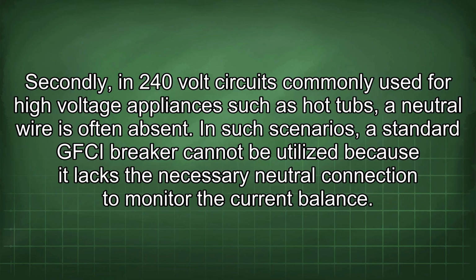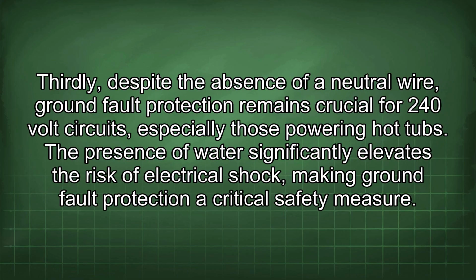Secondly, in 240-volt circuits commonly used for high-voltage appliances such as hot tubs, a neutral wire is often absent. In such scenarios, a standard GFCI breaker cannot be utilized because it lacks the necessary neutral connection to monitor the current balance. Thirdly, despite the absence of a neutral wire, ground fault protection remains crucial for 240-volt circuits, especially those powering hot tubs.